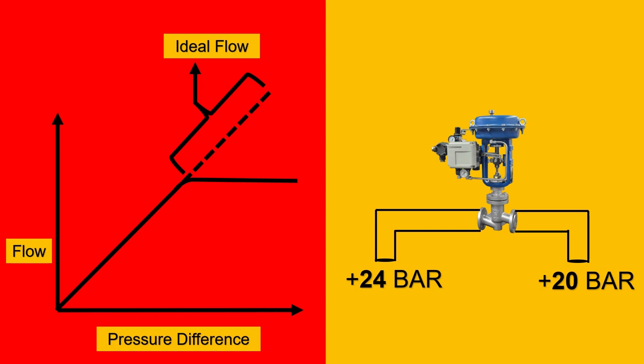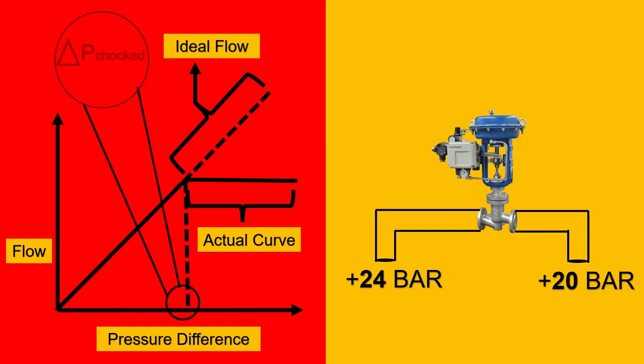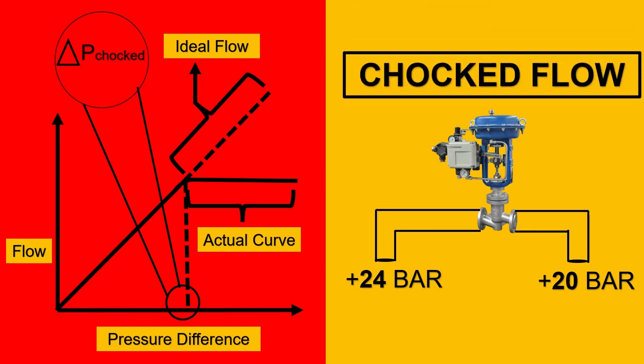But the ideal flow characteristics don't work as we saw in the electrical circuit as well. This point is the actual curve where the flow will not increase even though we increase the differential pressure across it. This phenomenon happens at a point where we call as the del p choked or the choked flow value beyond which even if you increase the pressure drop, there is going to be no increase in the flow and this phenomenon is called as choked flow.